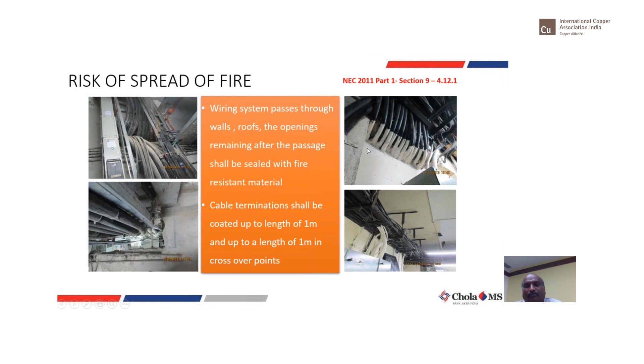So, safety by design, in all ways, with proper barriers. You find the shrouds which are available on the panel. When a new panel comes and you open the door, you will find all these barriers. But over time, one screw falls, then at the next maintenance a second screw is removed, at the third maintenance one more screw is removed, and at the fourth maintenance the barrier itself is removed and kept on the floor. The fifth time, next day morning, housekeeping will come, sweep it up and put it in the dustbin. So finally, within three to four months, the new panel is ripped apart and every conductor is exposed. And finally, some lizard is going to go in here or there, or there could be a flashover, loose bolts, and all of that.